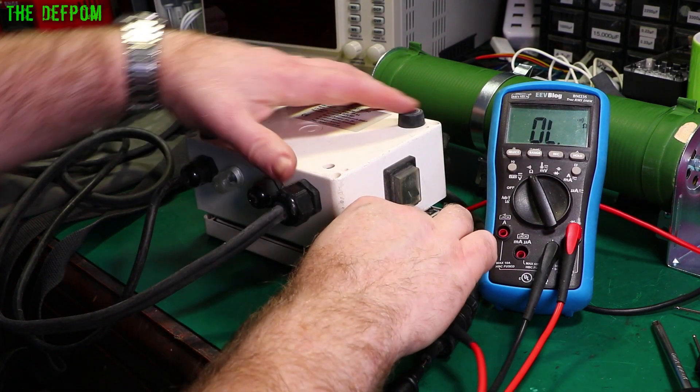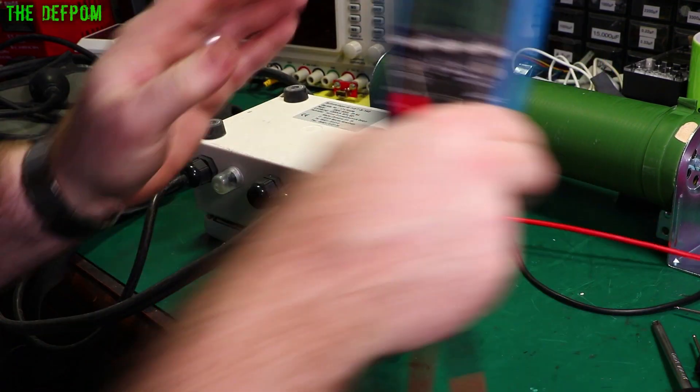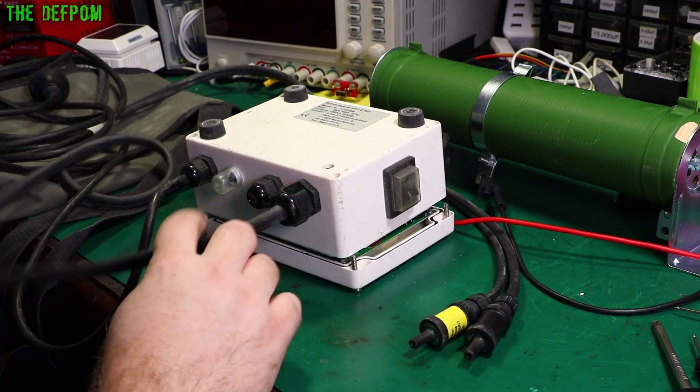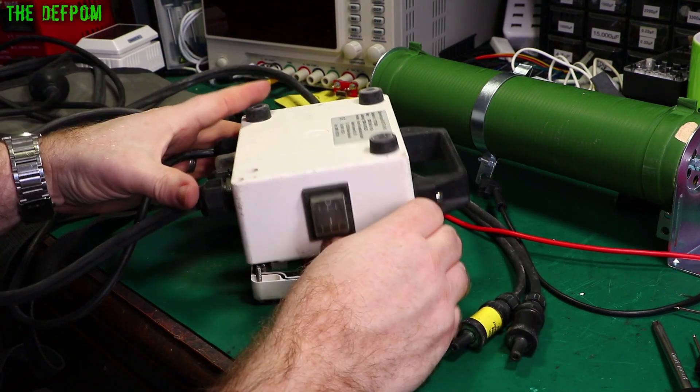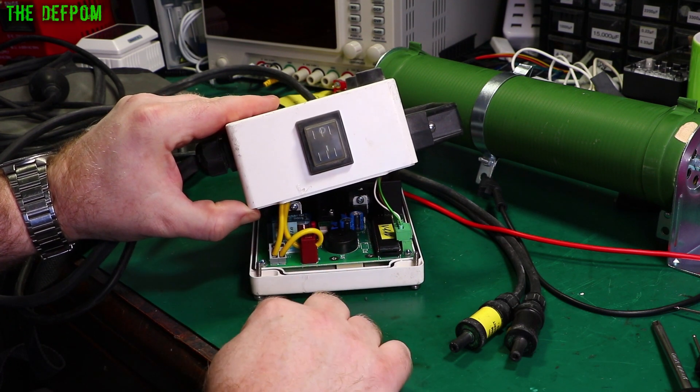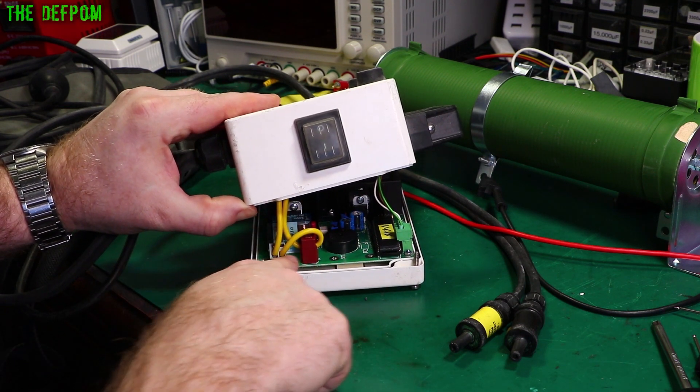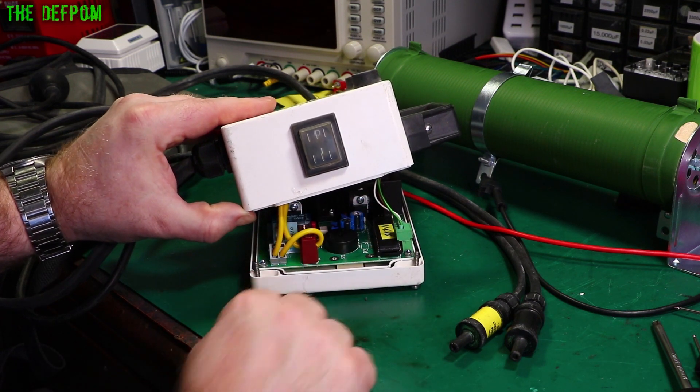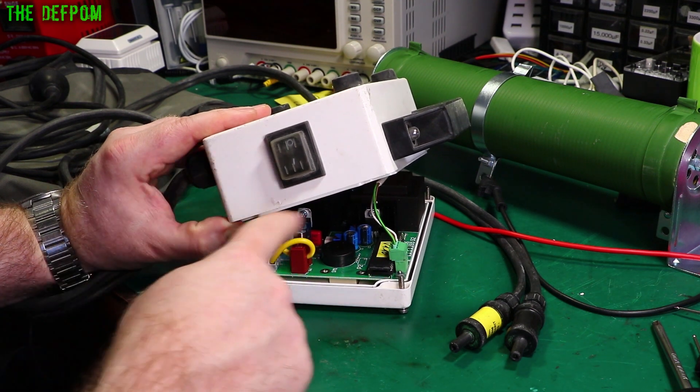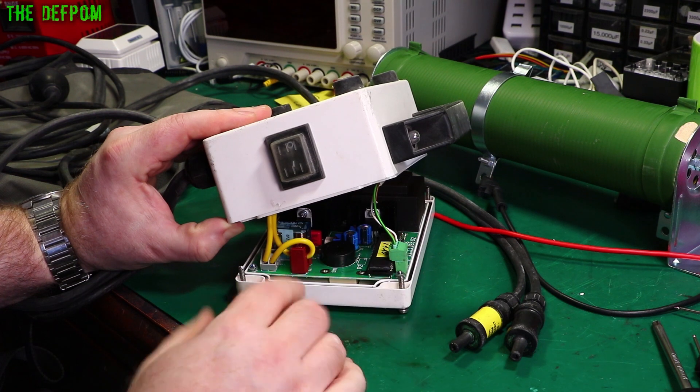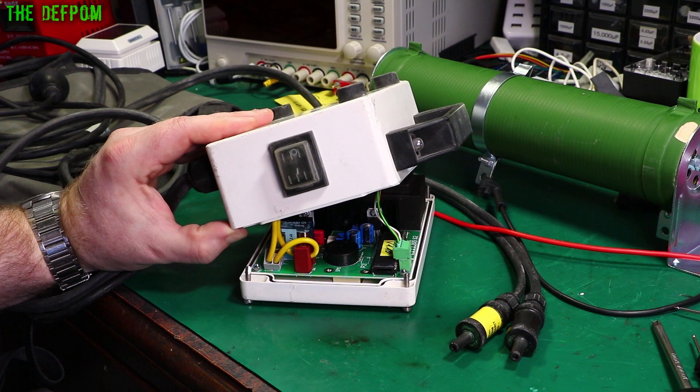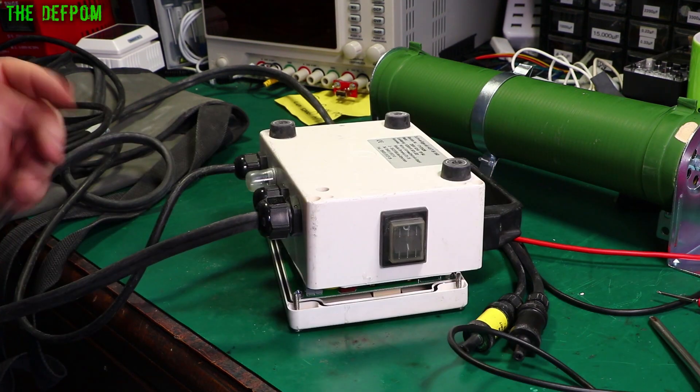So in order to fix this we need to strip all this piece apart and get that out and thread it through and put a new piece in. Well, I'm going to use the original cable, I'll just shorten it a little bit. It's not a big deal, but obviously you've got to go through this current sensor, stuff like that. Go through in a correct direction, so you have to make sure the cable comes through from the outside through to the inside. So I mustn't forget to get that correct, because I'm obviously going to have to disconnect these and push the whole thing through again. I need to make sure that you get the current sensing direction correct because it could matter, otherwise it might not work properly. So let's get this stripped down.